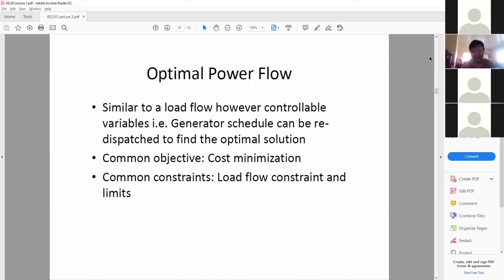Then you'll run, usually a power flow software, and eventually you'll determine how does power flow from generation to load, and you will eventually know, sobra pala yung kunwari 20 nga yung load ko pero 30 yung in-schedule kong gen. Upon performing the power flow through the network, lumalabas ang loss lang pala is let's say 3 megawatts. So you have 20 megawatt of load, and then for power to flow from the generation to the load na 20, 3 ang losses, so sobra-sobra. 30 yung in-schedule mong generator, as opposed sa dapat 23, load plus loss.